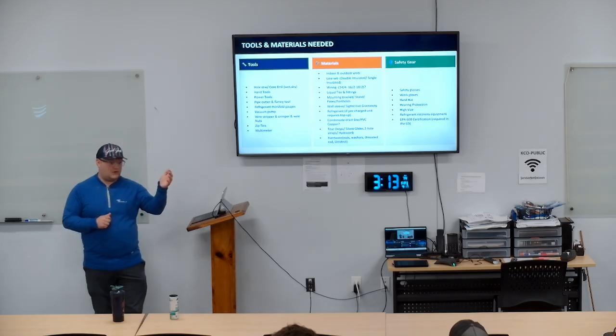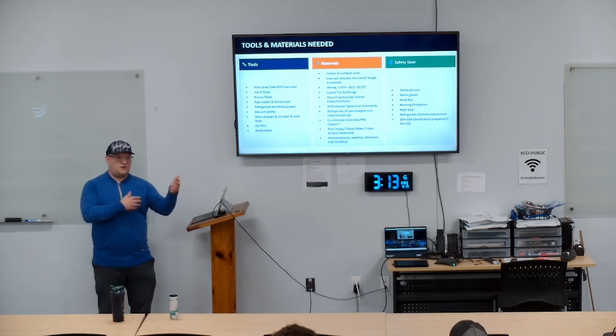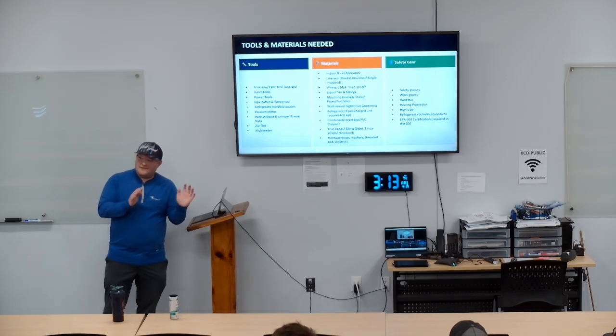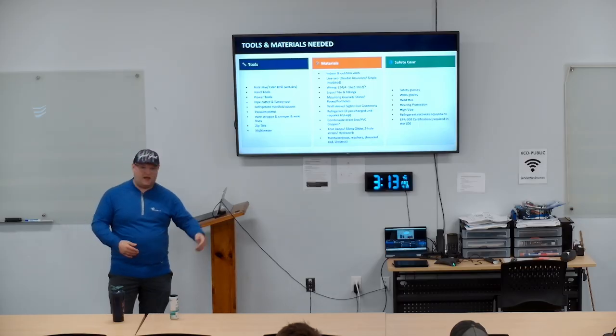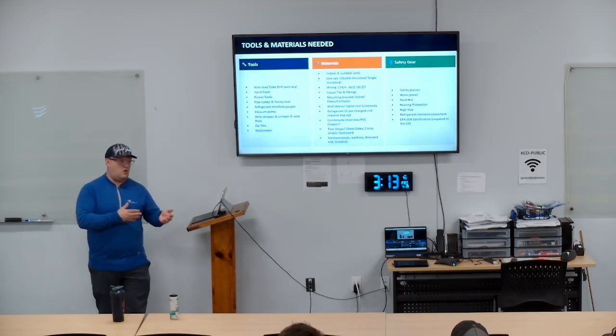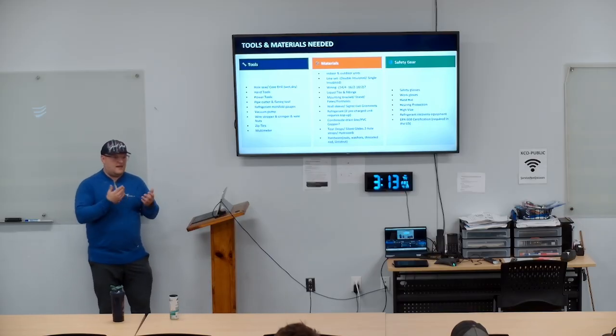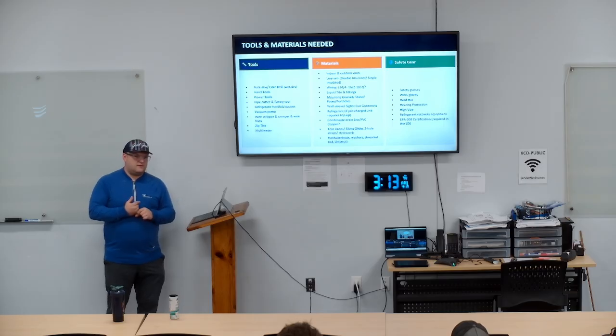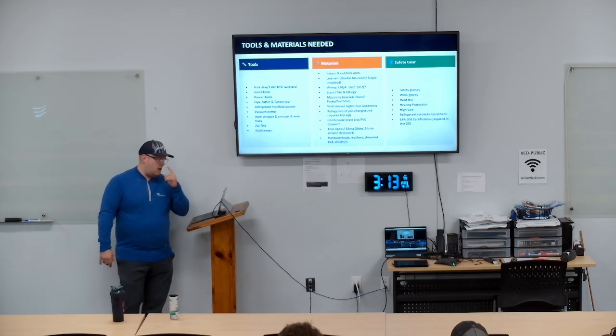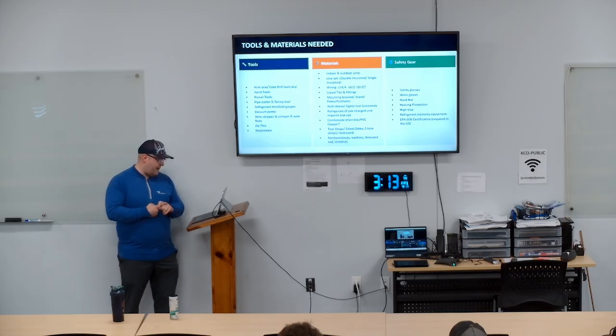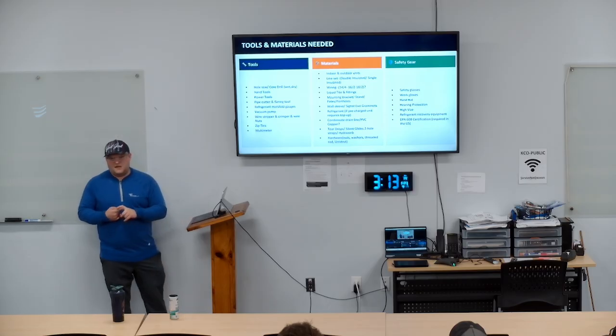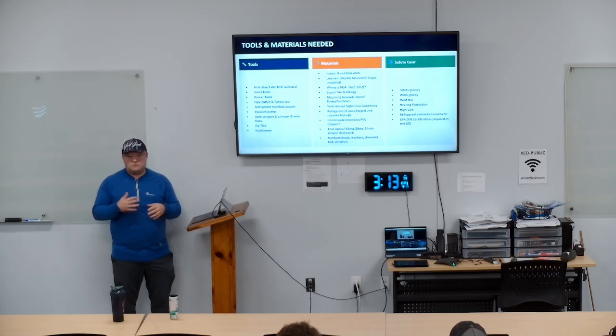So I get online and search up the unit model number that's on the PO, because you can't even look at the schedule because it changes, it adjusted. We don't have that unit, but we can get you this one. So I go to a PO of an actual unit we have that's coming and I'll look that up. You can find it online. An install manual comes online. So, yeah, outside of that, mounting brackets: if it's a heat pump, it's got to be off the ground. Because what happens is it'll go into defrost mode in the winter, and as that water pours off, if it's not off the ground, it starts to accumulate on the bottom, freeze, and crack your coil.